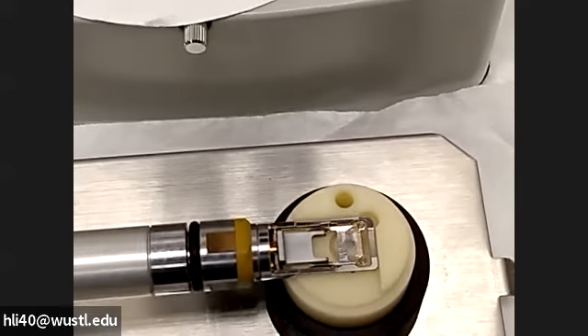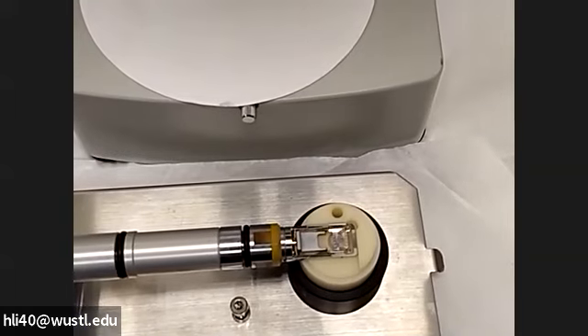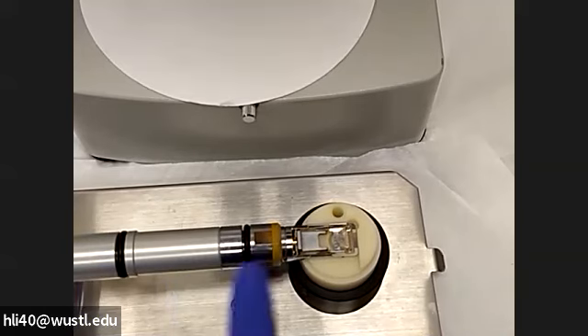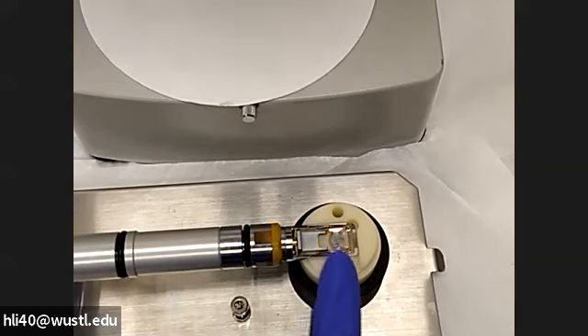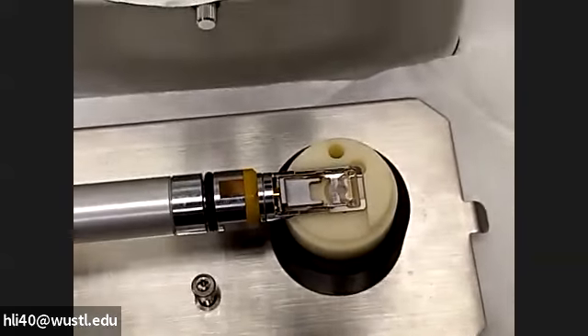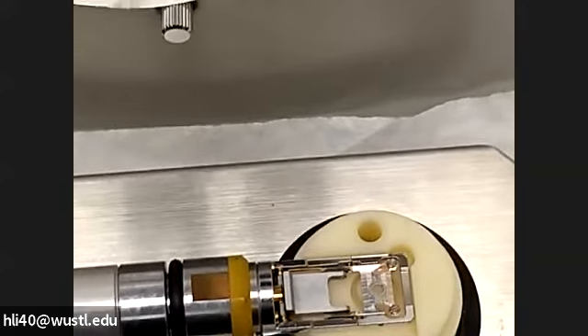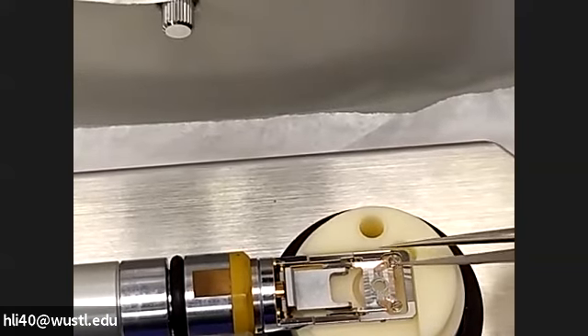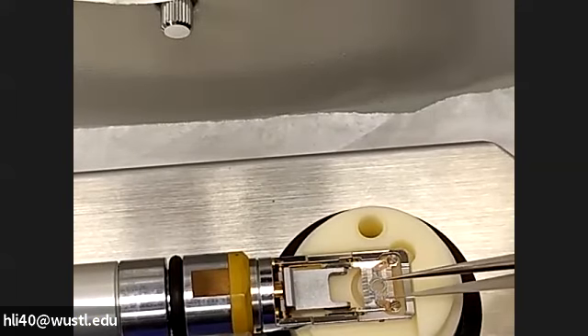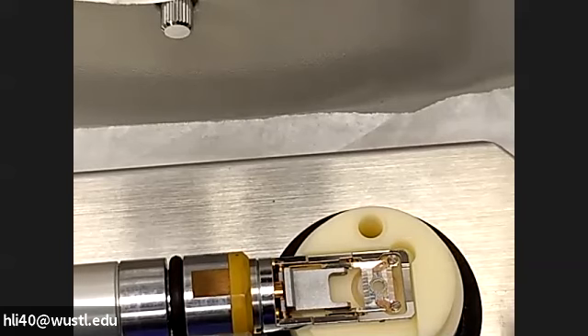So we're working on a tip here. No matter which holder, you can hold the left side, but don't touch the O-ring, don't touch this side. Don't poke or break the tip, okay? So we need to be very careful. I'm going to zoom into the tip only. On the tip, you will see we have two clips here, one and the other one. And we have this shaped washer and another O-shaped washer underneath. I'm going to take this out, okay?